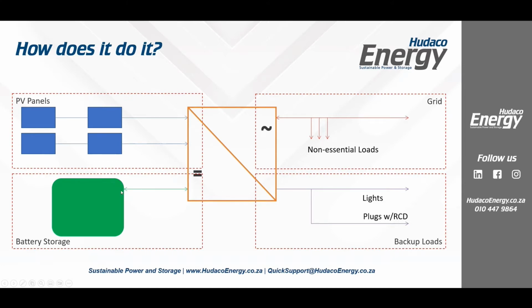Well, why would I want to do that, you might say? Well, we've done the calculations, and it's about R0.66 per kilowatt hour to generate your own power, save it and use it again. So in self-consumption mode, I'm generating my power, I'm storing my power, and these batteries are 6,000 cycles. The guarantee is 6,000 cycles on these batteries. We want to cycle them. We actually want to use it. It's better and cheaper for me to create my own energy, to store my own energy, and to use my own energy at R0.66 than it is to buy more energy from grid, even after hours, at R2.66 or R2.88 or whatever it is now. So it makes a lot of sense for us to cycle and to use the batteries.